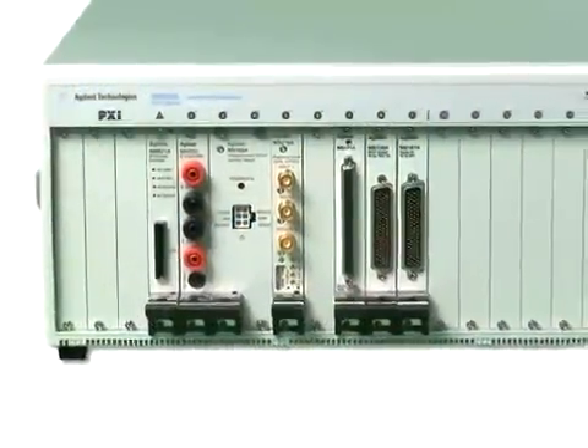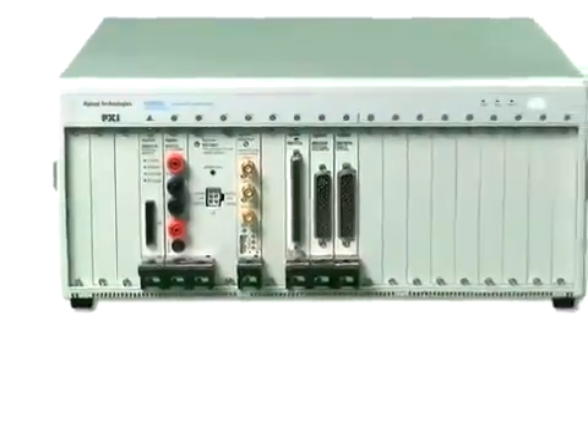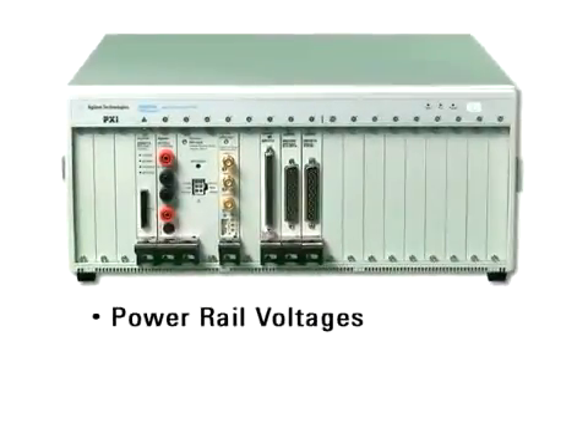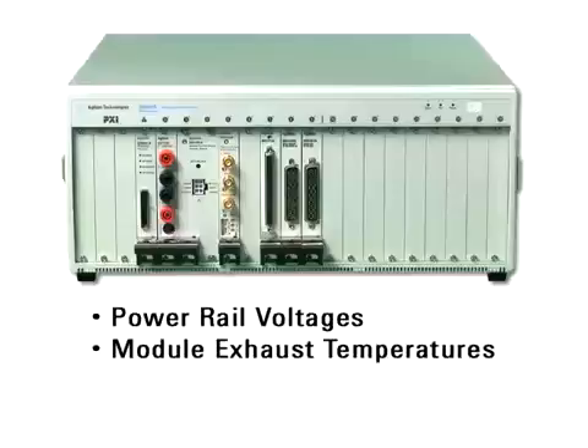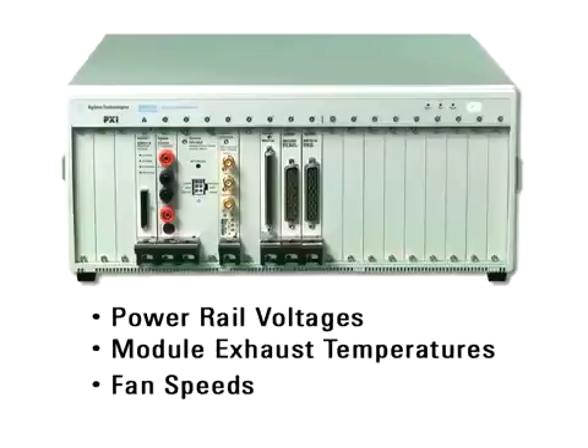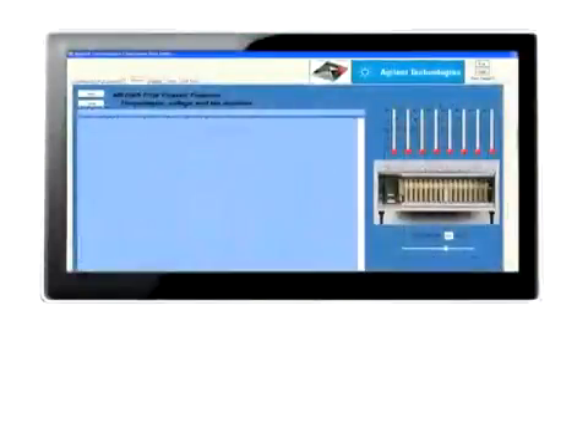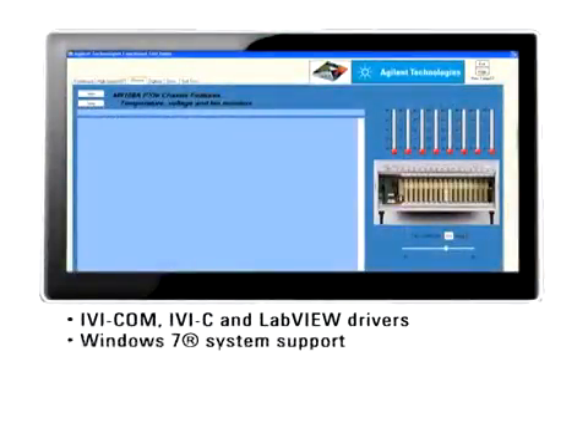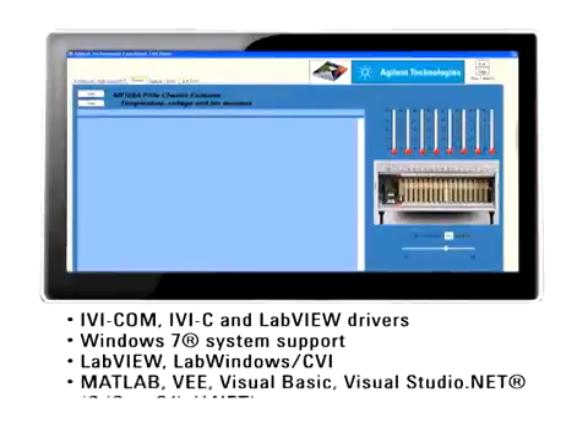This solution offers a complete set of chassis monitoring functions for power rail voltages, module exhaust temperatures, and fan speeds. These tools can be used to ensure repeatable and reliable test results. A rich set of IVI commands provides access to the M9018A's built-in monitoring features. We'll demonstrate these features using this example chassis data logger program built upon these IVI commands.